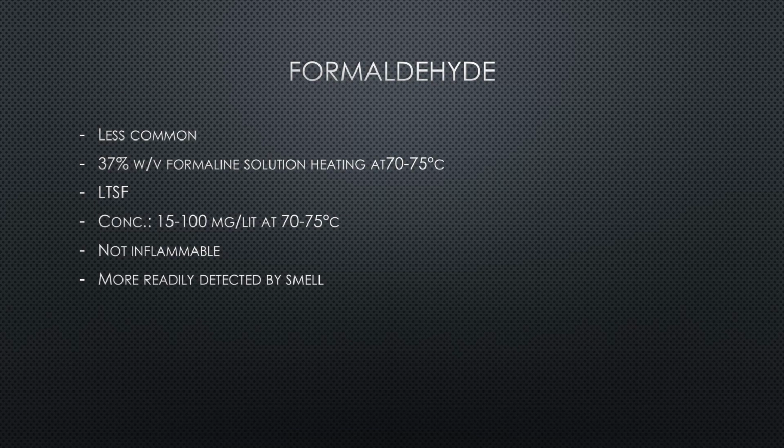Formaldehyde can be detected with the smell, but ethylene oxide cannot be detected by the smell. So if there is a small amount of formaldehyde, it can be detected in the environment, but if ethylene oxide is present in the environment, it cannot be detected. So this is quite an advantage of formaldehyde, and it also has a shorter cycle. This formaldehyde is used for the sterilization of other packaging material like papers or cotton fabrics, because its penetration power is meant for that capacity only. It is not going to penetrate the rubbers and plastic. It is going to penetrate only the paper and cardboards.